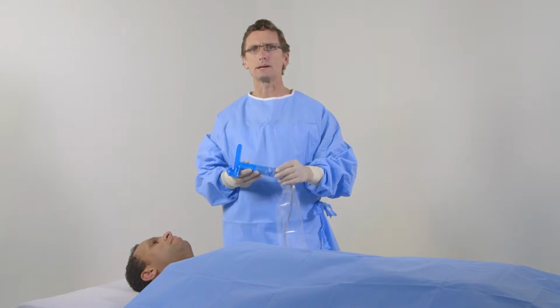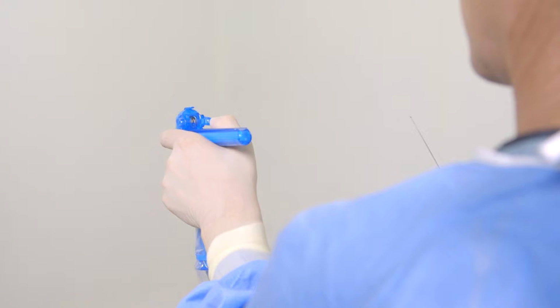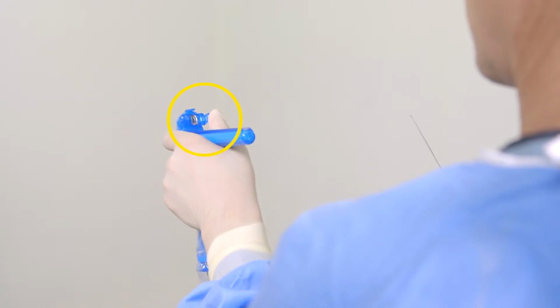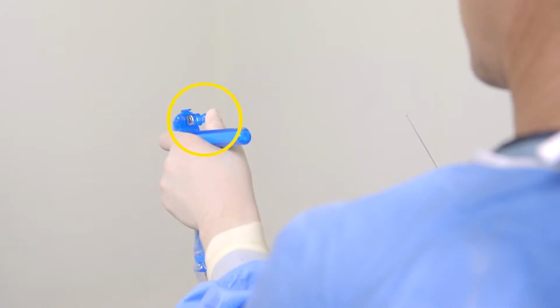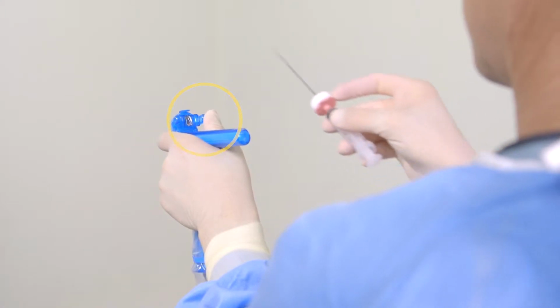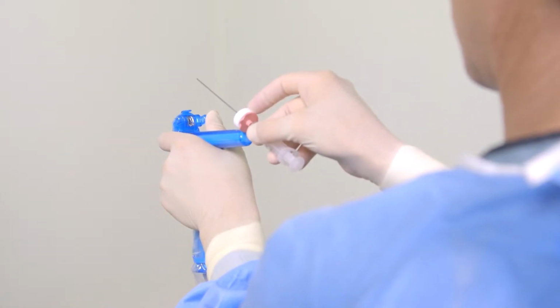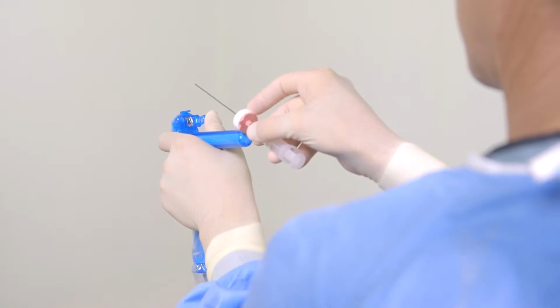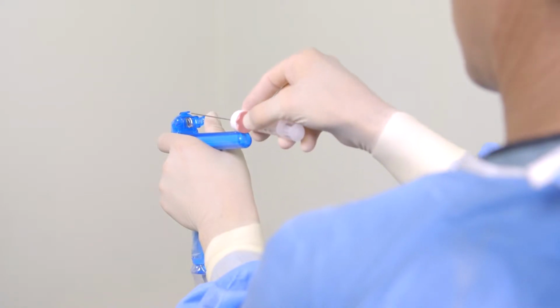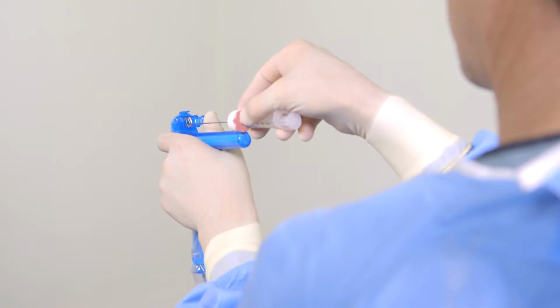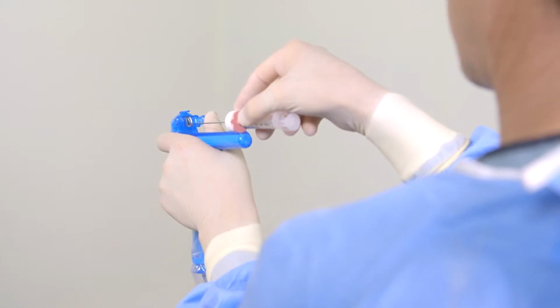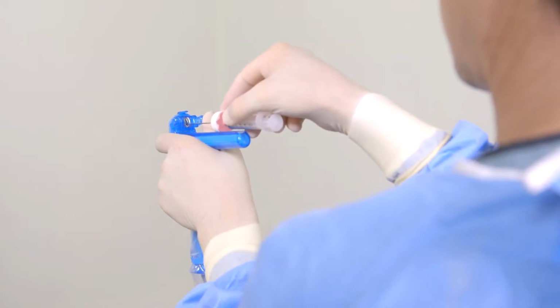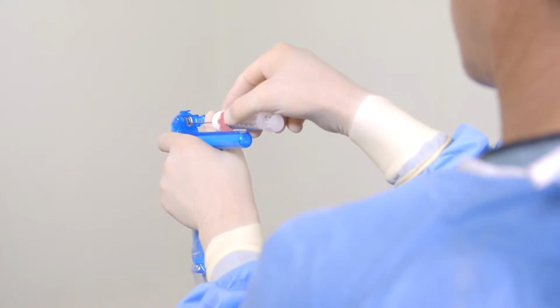the needle into the integral needle guide. Start preloading the needle by rotating the needle clamp fully forward with your thumb to the open position, such that the needle guide opening is unobstructed. Then, place the magnet against the proximal end of the magnet rail to stabilize the needle as you move the needle tip into alignment with the needle guide opening. To maintain needle sharpness, avoid hitting the needle tip against any surface as it is preloaded into the needle guide.